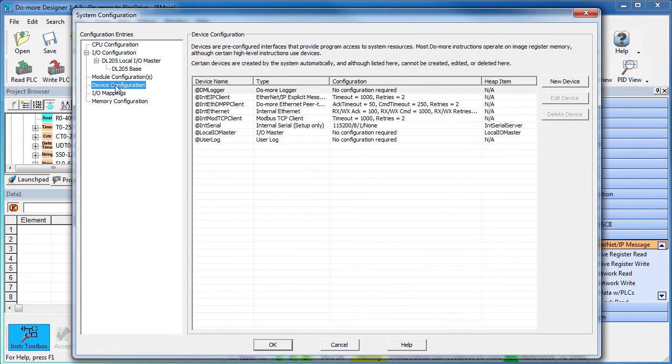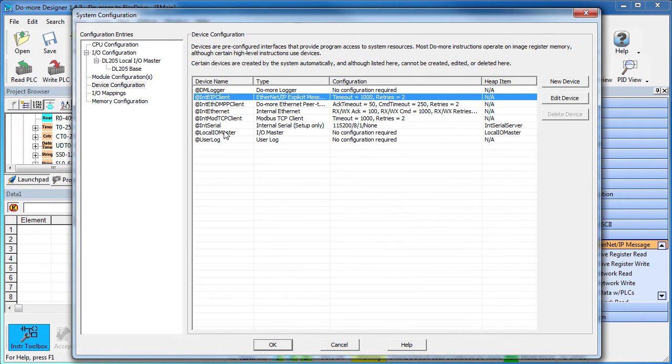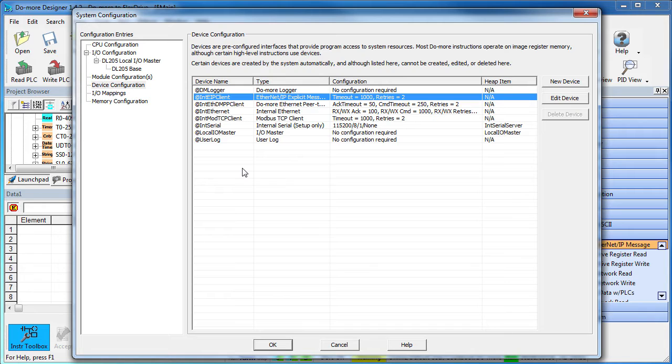It does create a new device. And while we could use this built-in Ethernet IP device, it's much better to create a separate new device for each piece of Ethernet IP hardware. Otherwise, one device will have to manage multiple TCP IP connections which can slow things down.